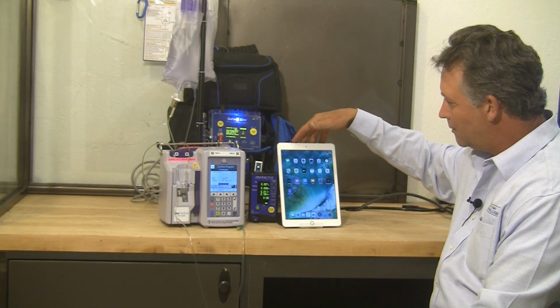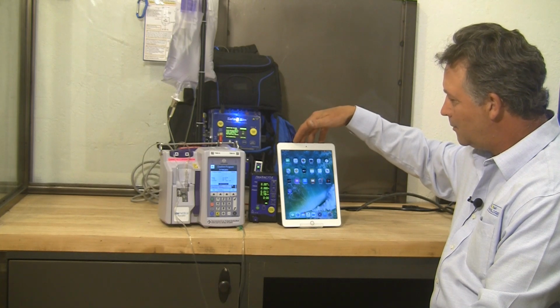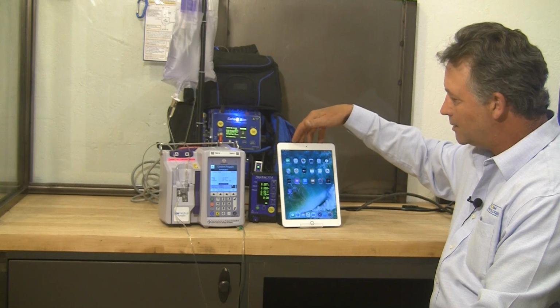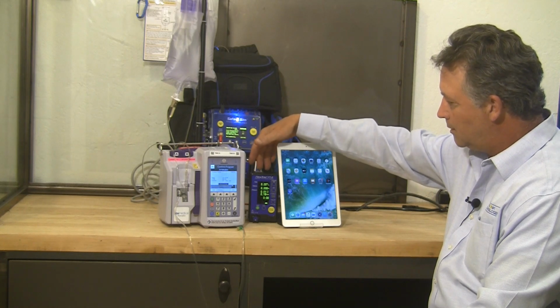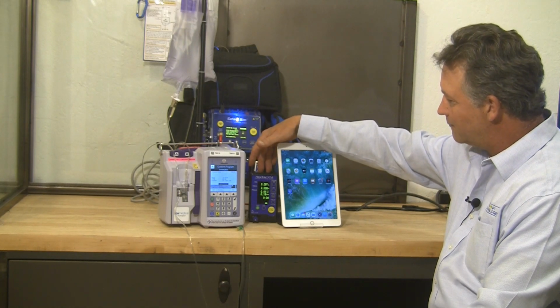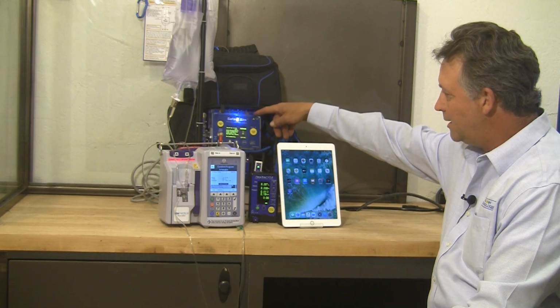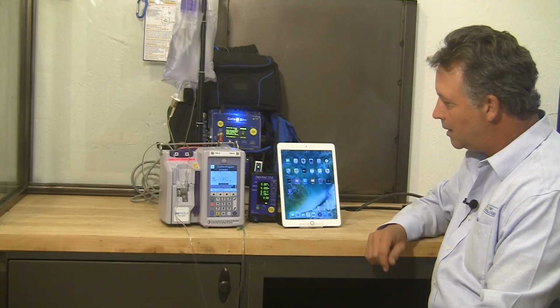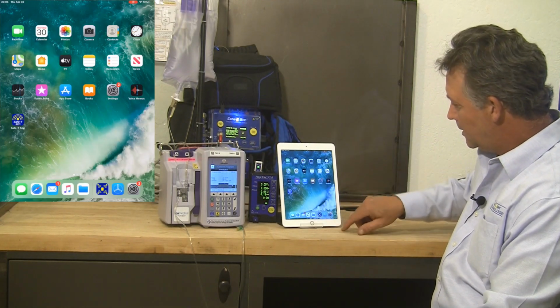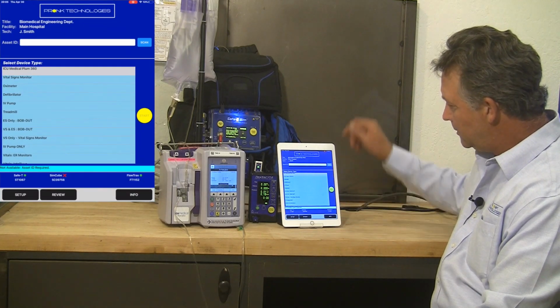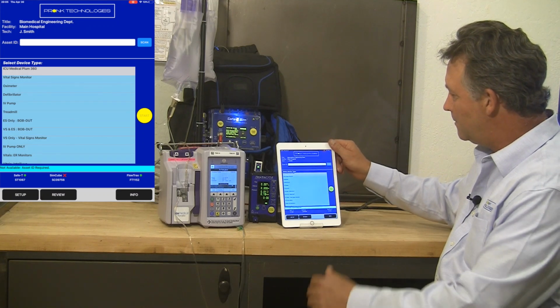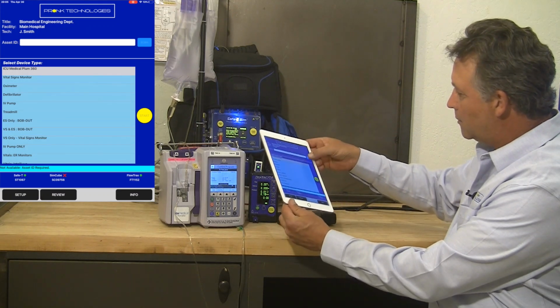But we're going to walk through an IV pump test using an iOS device that is wirelessly communicating to both an IV pump analyzer, in this case the FlowTrax, and a safety analyzer, the Safety Sim, both made by Pronk Technologies. So from my iOS device, I'm going to launch the app. And from the app, the first step I want to take when I'm testing an IV pump is to go ahead and do a barcode scan directly from the iOS camera.